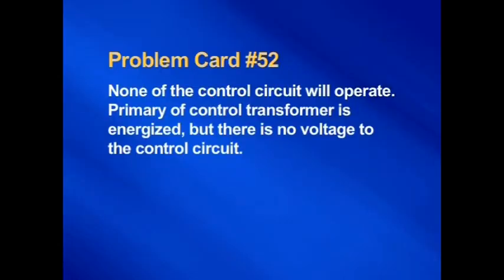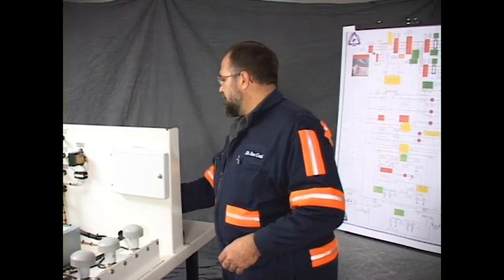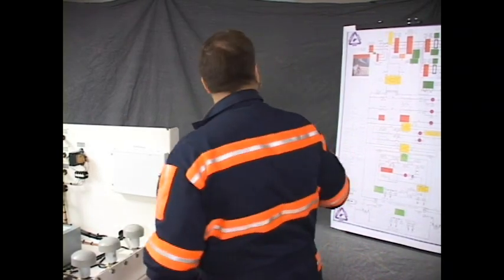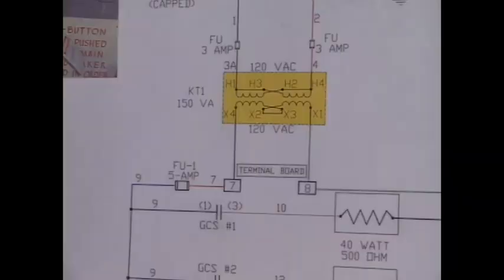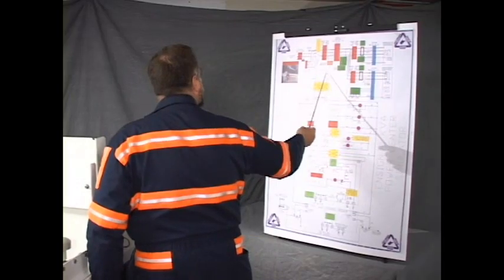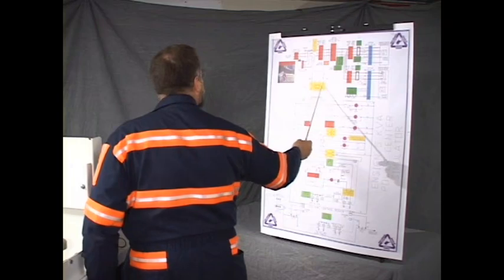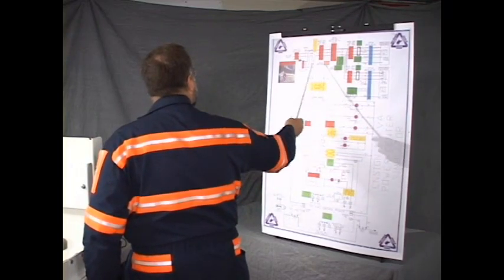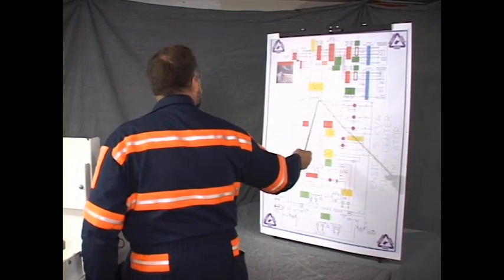The second problem card, number 52. If you should draw this problem, it would read, none of the control circuit will operate. The primary of the control transformer KT1 is energized, but there is no voltage on the control circuit. Again, as we referred to earlier, KT1 on our drawing is here. The primary, stated in the problem card, is energized, so the problem won't lie in that area. But it says none of the control circuit is energized.